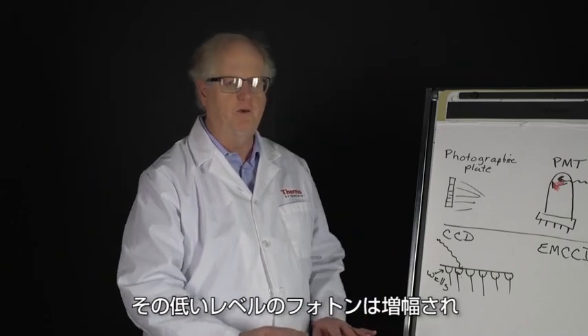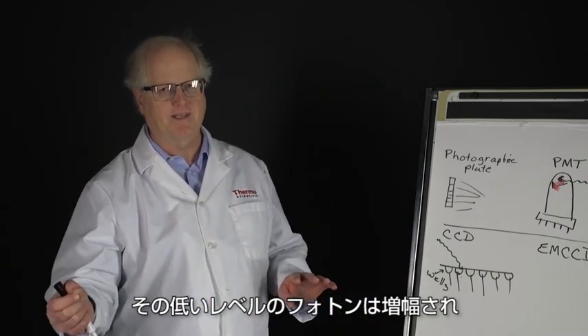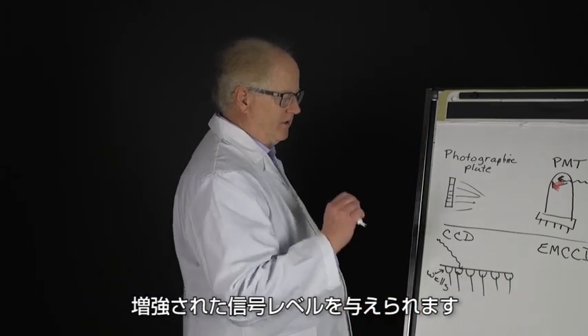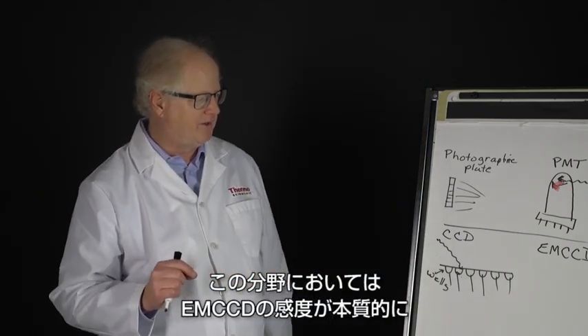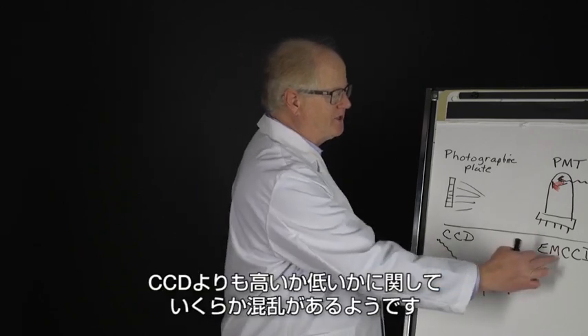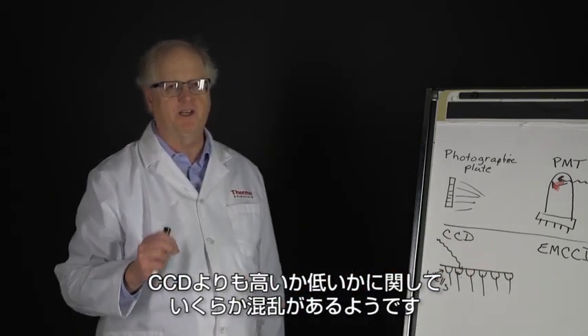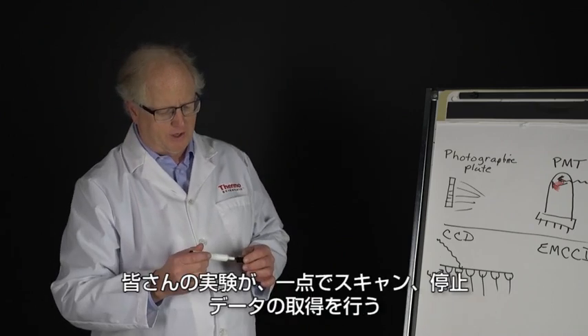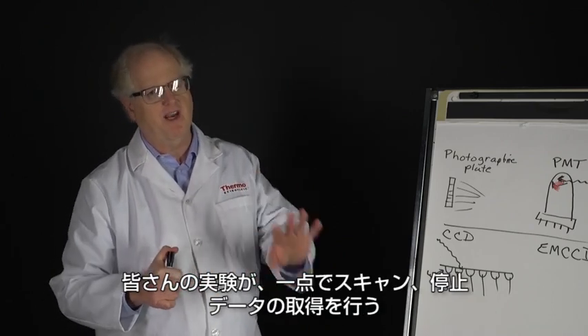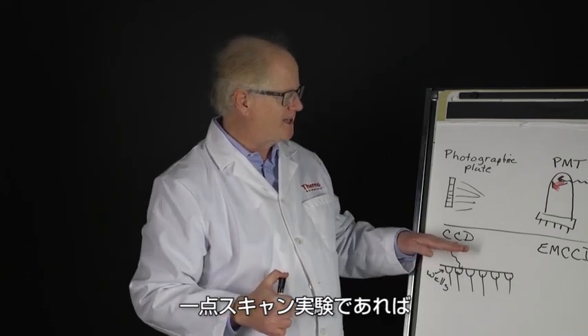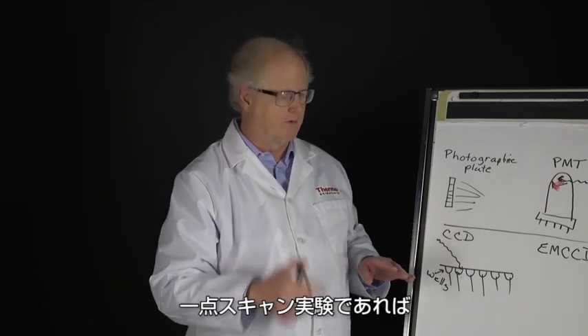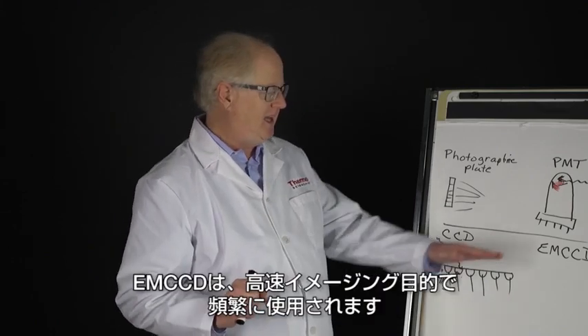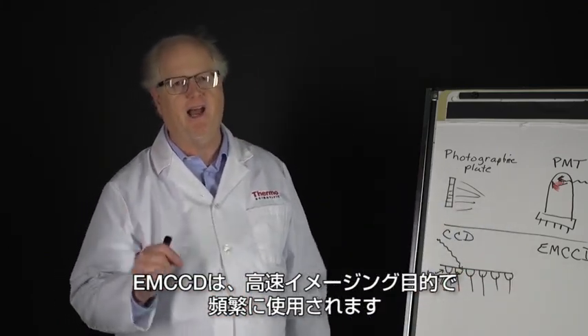There is some confusion in the field as to whether or not an EMCCD is inherently more sensitive than a CCD. The answer is it depends upon your experiment. If your experiment is a single point scanning experiment where you're going to scan, stop, and collect data over a single point, a CCD is perfect for that. The EMCCD is heavily used in high-speed imaging purposes.